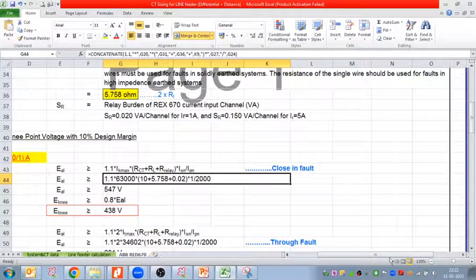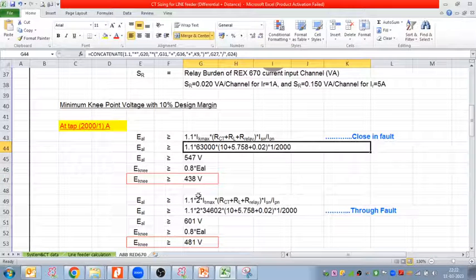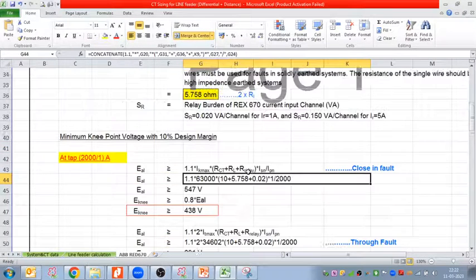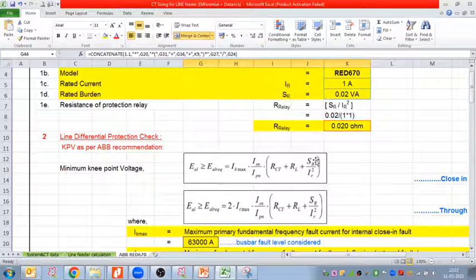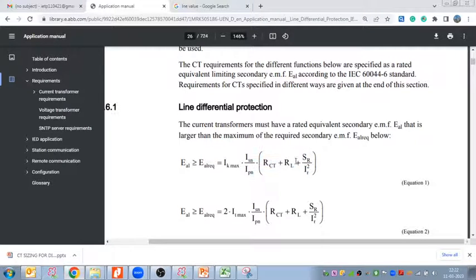Let me zoom out so that you can see what we enter here. So 63 kA, IK max, into RCT 10 ohm of the CT resistance, plus RL, my lead resistance, plus RR, my relay resistance. If you see here, SR divided by IR square, what does it give? It gives the burden, the resistance, right now. It gives the resistance only.